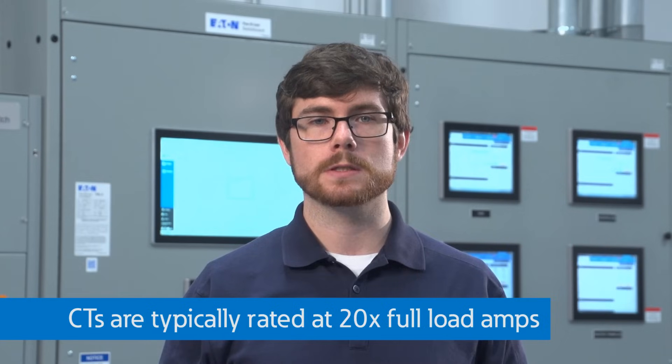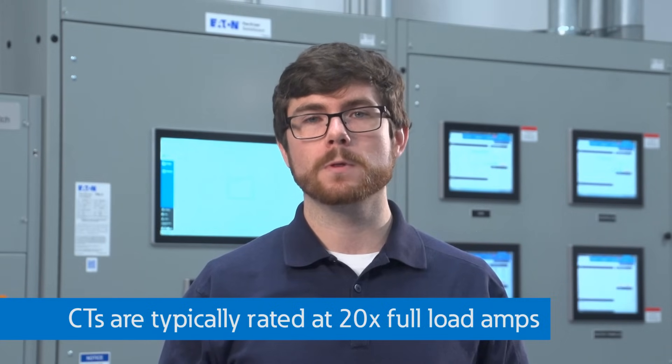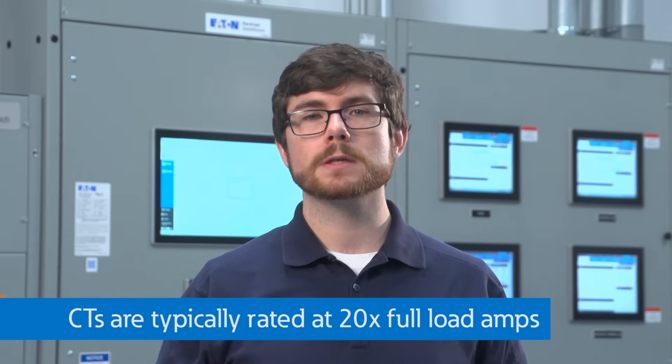For all protection applications, CTs must be rated to accurately measure the high currents that are possible during fault conditions, usually 20 times full load amps, so that the breakers can trip in the proper sequence without saturating which yields an incorrect result.